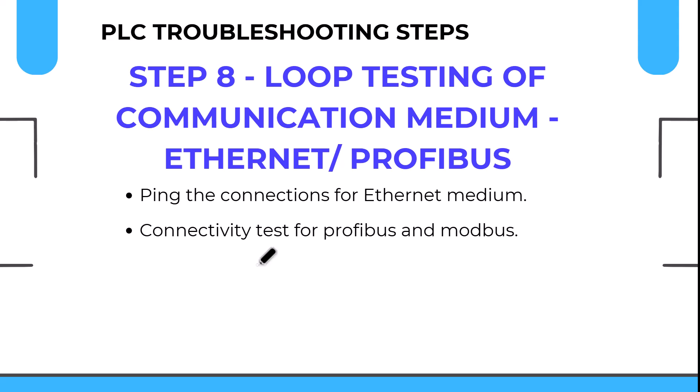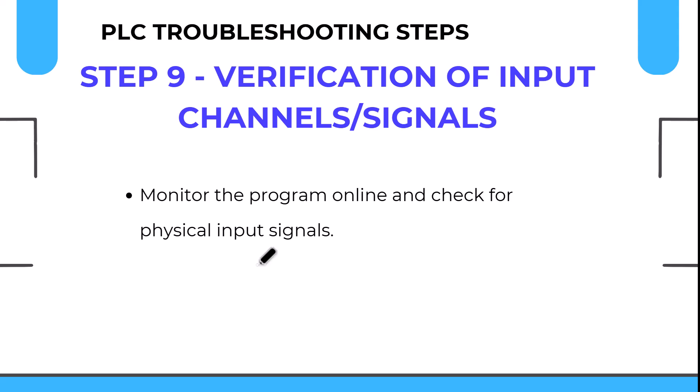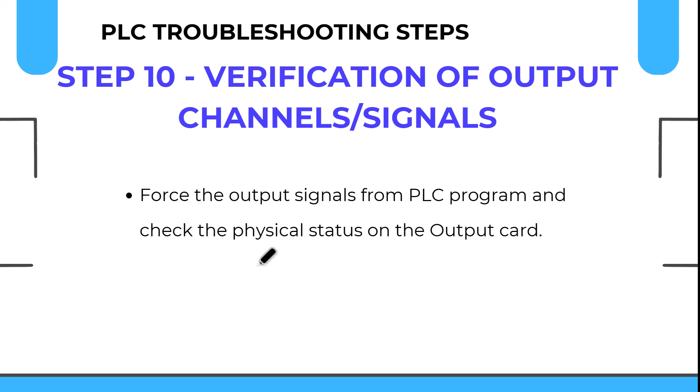Loop testing is a key aspect of PLC troubleshooting — whether the communication medium is Ethernet, Profibus, Modbus, or fiber optic (tested with a light signal). If a technician reports that a digital or analog signal is arriving at the PLC input card, go to the hardware monitoring in the PLC software and verify whether that specific signal is actually present on the input card. Verification of input channels and signals is mandatory. A channel may become faulty due to an abnormal signal arriving at the input card.